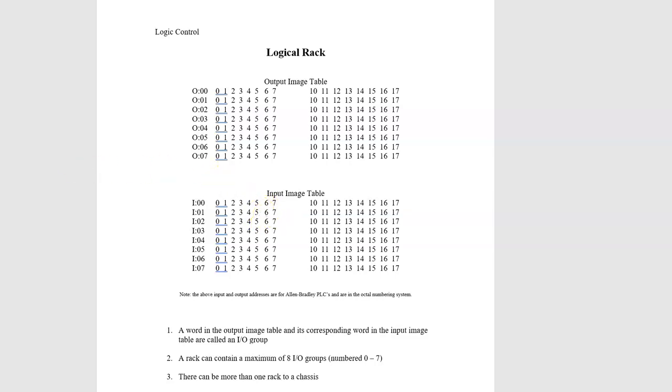The reason I'm bringing this up, though, is because when we talked about this, we looked at the numbering system here. Look at how this is numbered. It starts with 0, first of all. When I count each bit position, it starts at 0. And even when I count the output, these are the output modules, they reflect the output modules. Now remember, this is all in memory, so it's not a physical module, but this is mapped to a specific output module on the PLC. So output module 0, 0, and then it starts from 0 and counts up to 7. So there's 8 rows here, but notice that we start counting from 0.